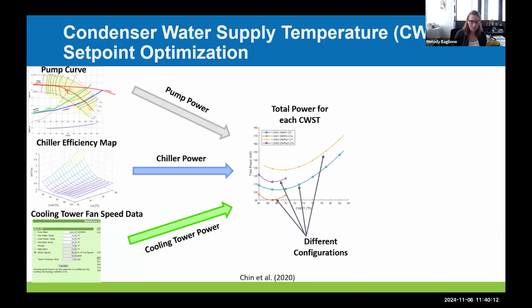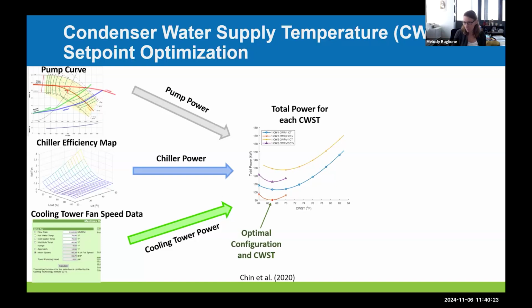They iterated for a number of different condenser water supply temperatures and found the optimal configuration and optimal set point under various load conditions. This is just one example load condition.